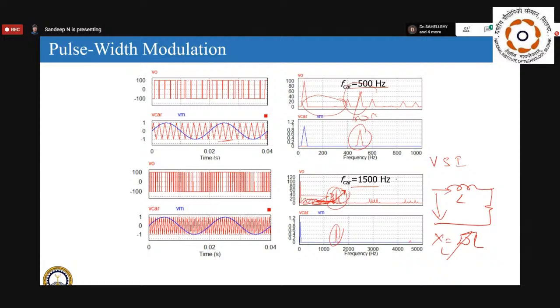That is the advantage of increasing the carrier frequency. If the inverter operates at higher carrier frequency, the dominant harmonics also get shifted to that frequency, and hence you require a smaller filter to filter out these harmonics. That means you are increasing omega, so for a given XL value, you can reduce L. If you fix XL, as omega increases, you can reduce the value of L, which reduces the size of the inverter or the filter.